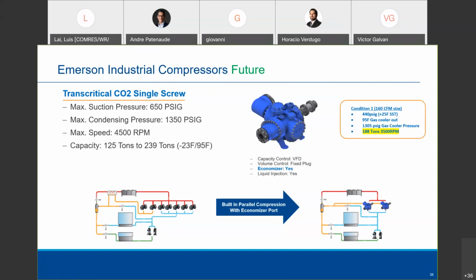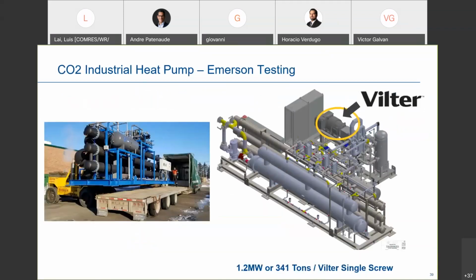Well, what this screw would enable us to do is have one or two for redundancy in parallel. And you can see here on the left, I've got parallel compressors. I'm showing two. So these are extra suction to come into these parallel compressors. Well, this screw model has the economizer port where we could leverage that parallel compression and digest that gas in an intermediate port, like we do with almost our EVI type of scroll. You're bringing in that vapor into a mid pocket. You're digesting it. It helps to cool, but it also provides you some system advantages. So that's kind of cool to look at from an advantage perspective.